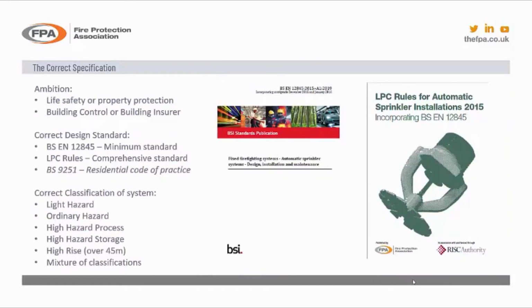So moving on and going into these slides in more detail, what is the ambition of the system? Well, the ambition of the system is derived from why is the sprinkler system required? Is it required for life safety or is it required for property protection? Who's actually asked for the sprinkler system? Is it a legal requirement? Is it a legislative requirement? Is it to satisfy building control or the building insurer? These key details must be realised at the very, very beginning of writing the specification, because there is a major difference between the life safety requirement and property protection requirement.